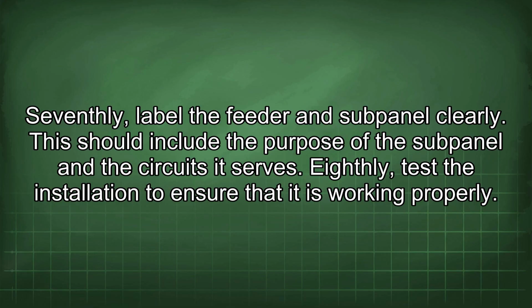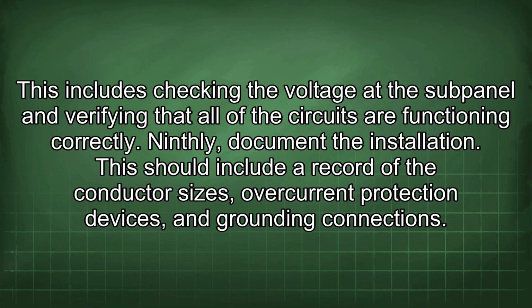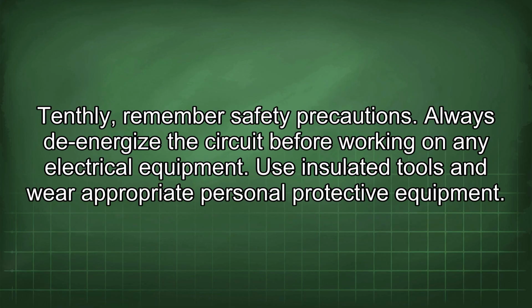Eighthly, test the installation to ensure that it is working properly. This includes checking the voltage at the subpanel and verifying that all of the circuits are functioning correctly. Ninthly, document the installation. This should include a record of the conductor sizes, overcurrent protection devices, and grounding connections. Tenthly, remember safety precautions. Always de-energize the circuit before working on any electrical equipment. Use insulated tools and wear appropriate personal protective equipment.